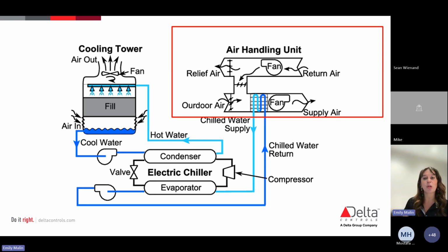This is all being controlled, like we said one slide ago, and I apologize, it's actually not on here, but this is all going to be controlled proportionately by that variable frequency drive. So that's going to be what tells it to speed up or slow down how much air needs to be pulled through there in order to get to that desired set point in our space. And again, another important piece of this is to make sure that once we reach that desired set point, we need to then close that valve to save our energy.